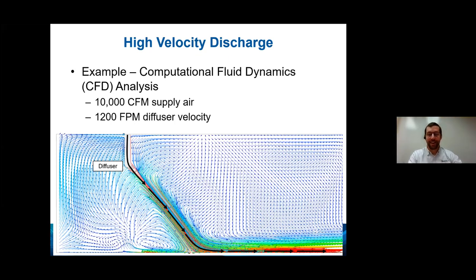The red arrows are the higher velocity, with green and then blue being the lower velocity in this example. You can see that air being thrown down to the floor, splashing along the floor. As it throws, as that air velocity moves through the stagnant air in the space, you can see how those arrows pull that air into the jet of high velocity air.